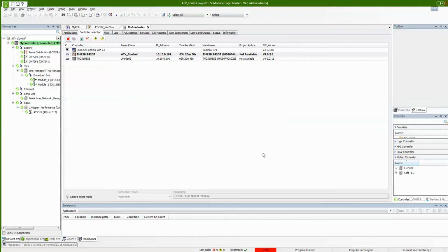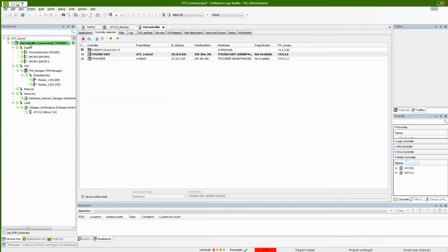Okay, and we can see on the left side, all my hardware is functional. There's a green circle to the left side of my interfaces, so everything's running. My CANopen is functional and my node is operational, so everything's good. Now I just need to start my PLC so I can execute my code. Now the PLC is in run.